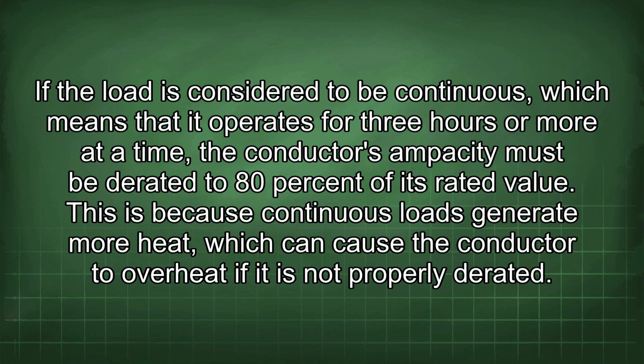If the load is considered to be continuous, which means that it operates for 3 hours or more at a time, the conductor's ampacity must be derated to 80% of its rated value. This is because continuous loads generate more heat, which can cause the conductor to overheat if it is not properly derated.